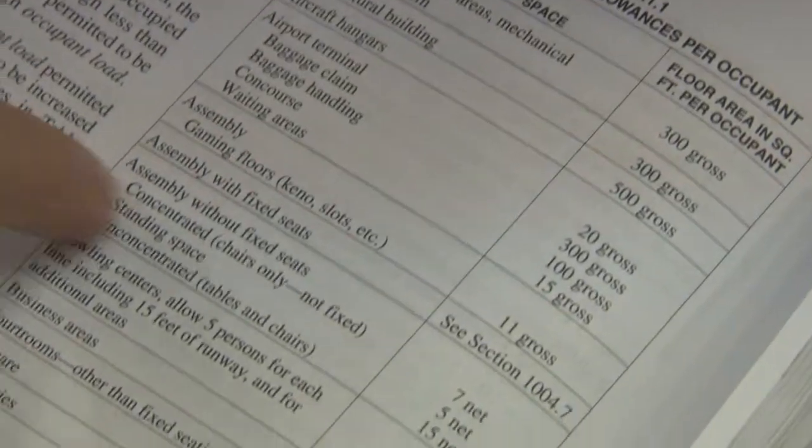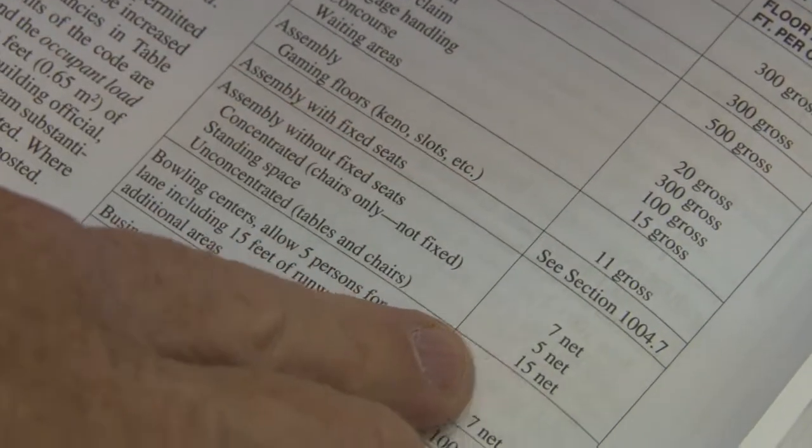and 15 square feet per person for tables and chairs. Whereas if we took that same shell and said, okay, it's a business occupancy just for doing routine business, it's going to be 100 square feet per person, and we don't take out fixed objects. It's just the gross square footage at 100. So it's really the use which determines the occupancy, and for the occupancy, you go to a chart of occupant loads for that given use, and it tells you how many square feet per person.